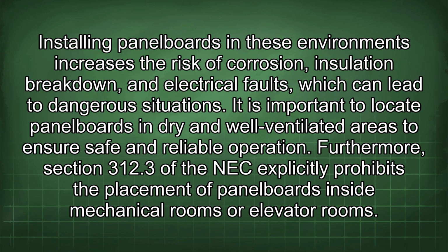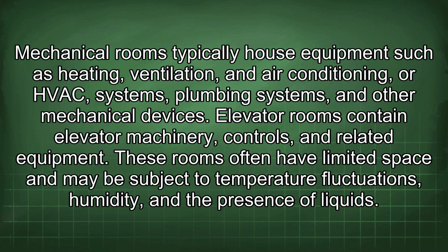Furthermore, Section 312.3 of the NEC explicitly prohibits the placement of panelboards inside mechanical rooms or elevator rooms. Mechanical rooms typically house equipment such as heating, ventilation, and air conditioning, or HVAC systems, plumbing systems, and other mechanical devices. Elevator rooms contain elevator machinery, controls, and related equipment. These rooms often have limited space and may be subject to temperature fluctuations, humidity, and the presence of liquids.